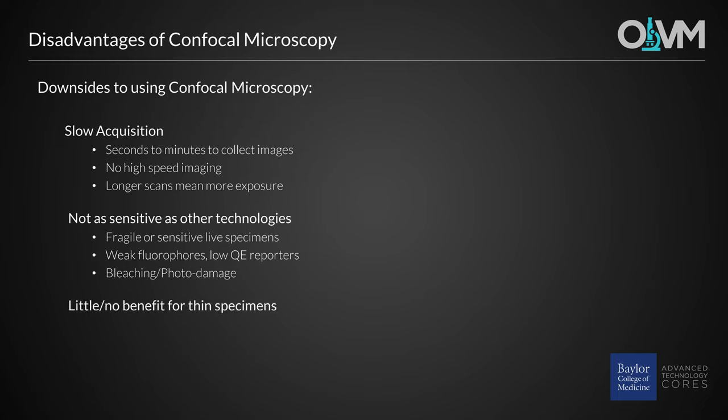Finally, thin specimens such as ultra-thin cryosections less than 10 microns thick, or specimens such as tissue culture cells will show little improvement in image quality with confocal microscopes compared to wide field, mainly because there really isn't that much out of focus signal to reject. Images collected of these types of specimens on wide field microscopes can be image processed to further improve contrast and resolution, such as with deconvolution software.